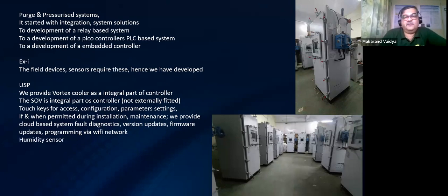I have introduced this, though it's not implemented yet - I'm still going through these studies. I realized that humidity or moisture is also a cause of fire, explosion, or hazard. So it came to my mind, why not add a humidity sensor in this enclosure to monitor condensation, even within a given day. In a 24-hour clock cycle you get a problem of condensation, and that condensation picks up toxic, flammable, or combustible gases. Then when the temperature rises, it releases those things, creating an environment that you can call a hazard.